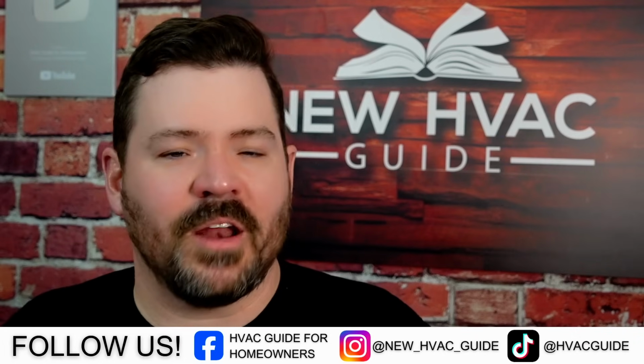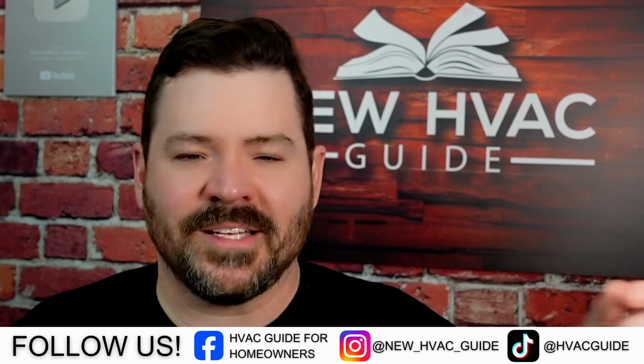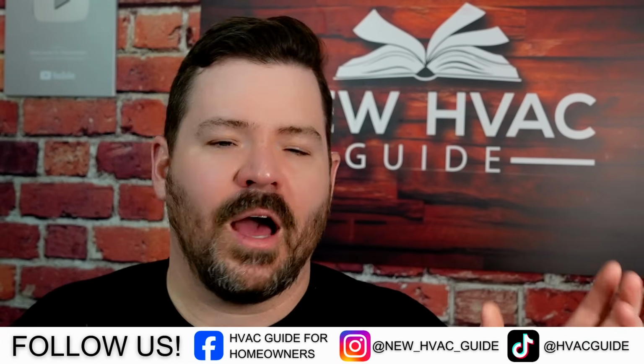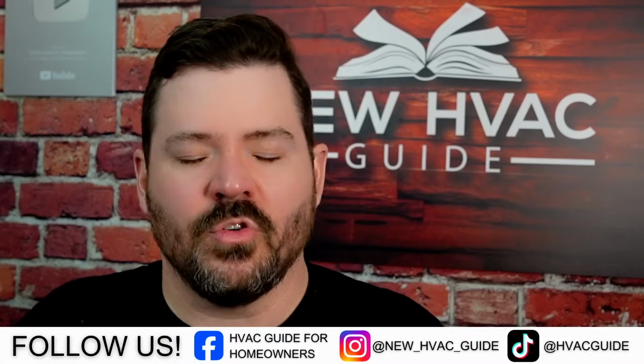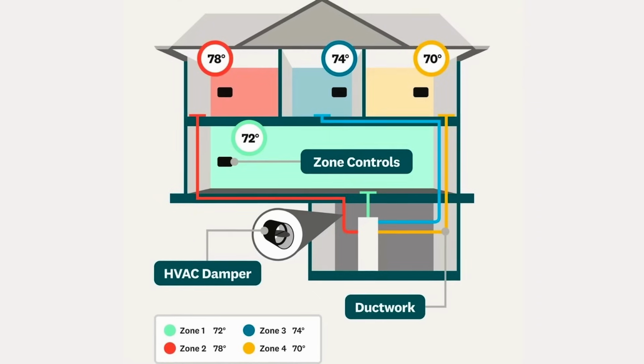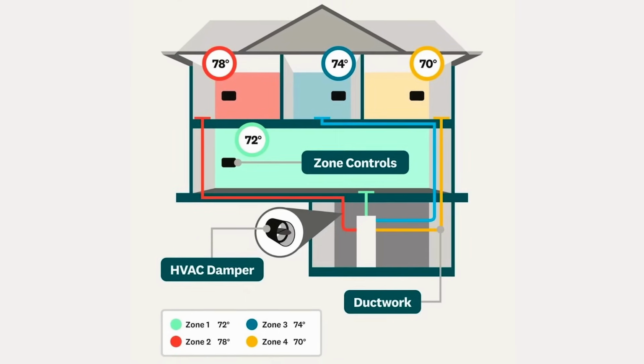I'm not saying there's never a place where you could close vents halfway, or that there aren't times when you could install zoning dampers that open and close based on your needs. All I'm saying is, without knowing what those pressures are, without knowing the static you're adding to that ductwork, you could be causing more harm than good.